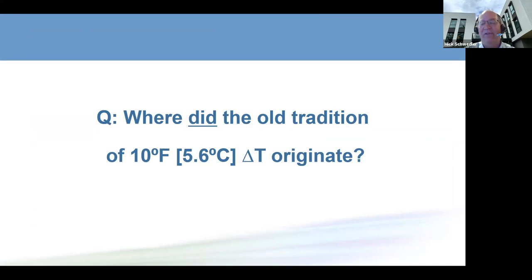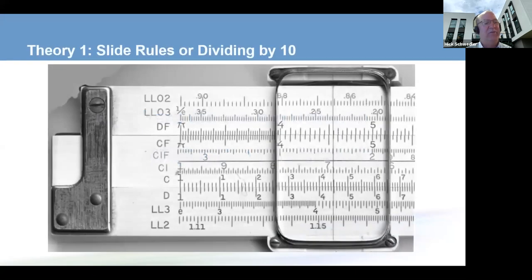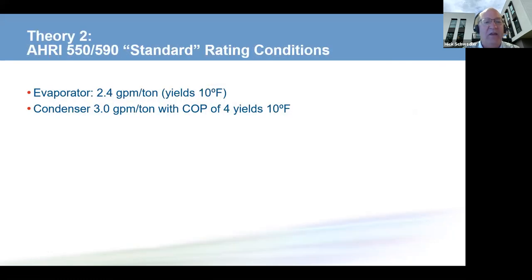Most of the time when I ask that question, the answer is slide rules. Something to do with dividing by 10. Well, that might be true, but if we had a 12 degree delta T, multiplying by 2 GPM per ton is easier than multiplying by 2.4 on the chilled water side. So maybe not. The second one is the AHRI rating standard 550-590 uses that as their standard conditions. Well, which is the chicken and which is the egg?